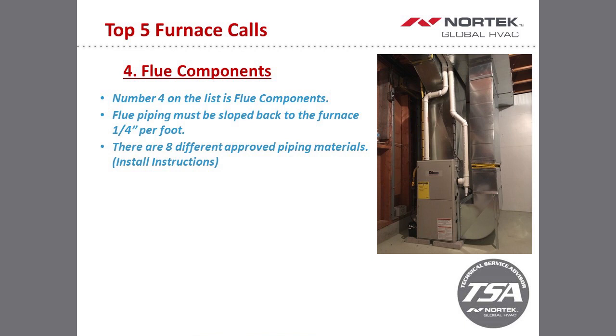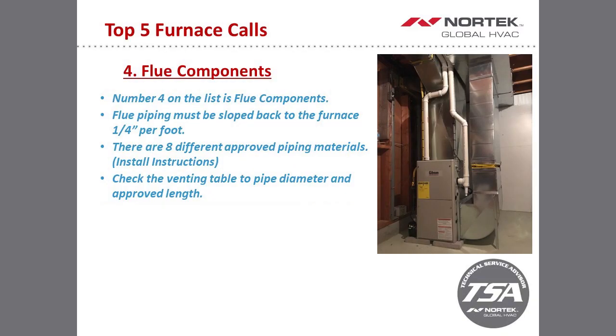Also, in regards to when do you go to 3-inch, you want to look at the vent table, and we'll look at that here in a second. You want to look at the vent table to determine if your furnace is only approved for 3-inch, because we have a lot of calls that come into tech with guys that are using 2-inch PVC pipe on either a 108,000 BTU furnace or a 120,000 BTU furnace. You cannot use 2-inch PVC pipe on those applications, but we'll look at that in a second. So just look at the vent table. You want to map out your piping run, see what roughly you'll be at from an overall linear feet standpoint, and then what your fittings will look like, from 90s and 45 fittings, to get your PVC outside.